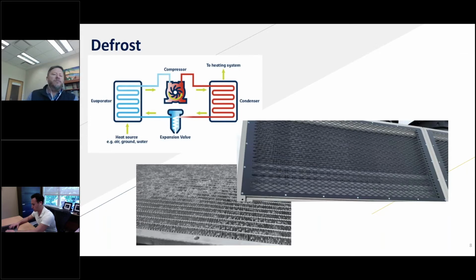As we look at that system with the evaporator, I'm pulling heat. If I'm heating, I'm not removing it from the building to cool, I'm removing it from our heat source, in this case air. It could be lots of things, though. It could be geothermal. There are multiple ways to get into that heat source. But for our purposes, we're talking about an air coil. We're going to be removing heat from the air, moving it with the compressor to the condenser, and rejecting it into the hot water loop, providing heating for our building. As we're running at elevated ambient temperatures, that just happens. As the ambient temperature is reduced, what we start seeing is we're driving that suction temperature down, right?